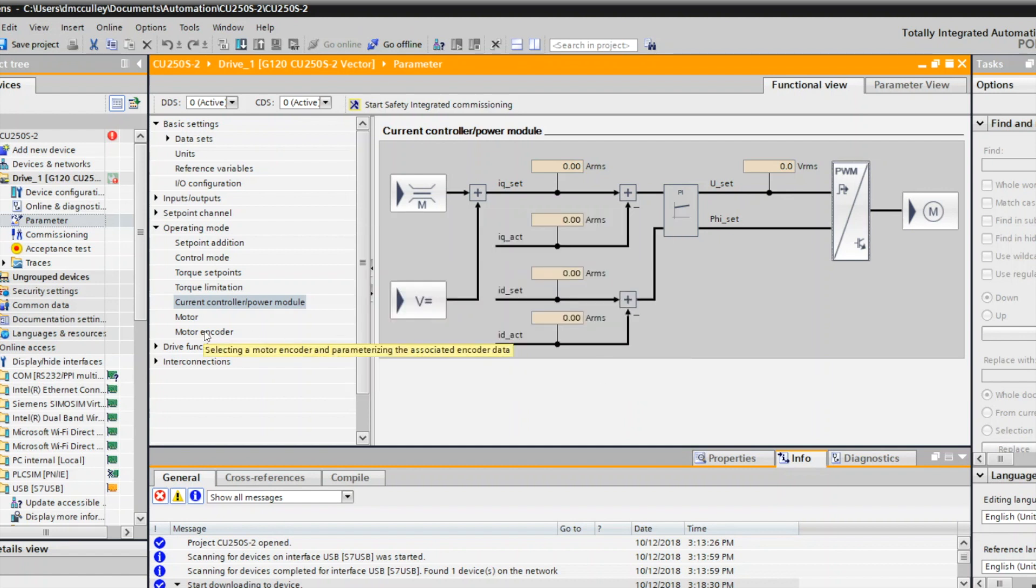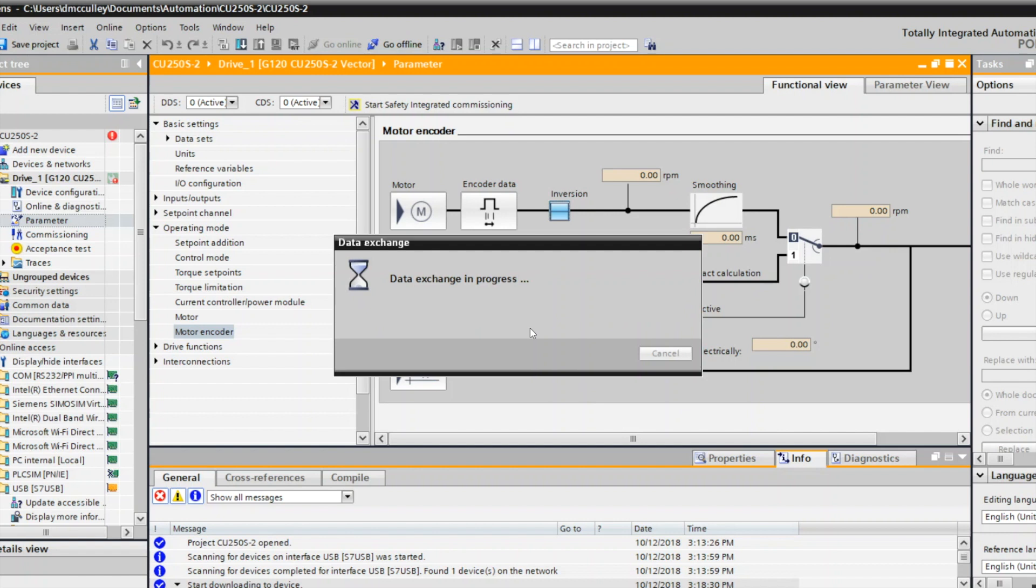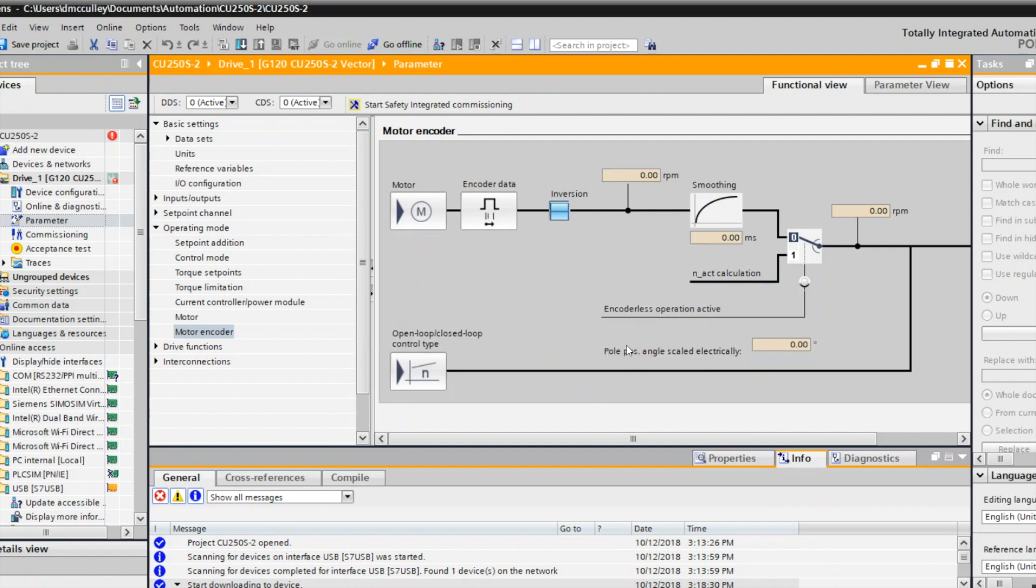But since you have a motor encoder, you need to also swap the motor encoder signal. If you go to motor encoder, there's this little inversion box. Check that, and now you've inverted the signal for the encoder. So the encoder and the motor are going in the same direction for a positive, and you're all done.